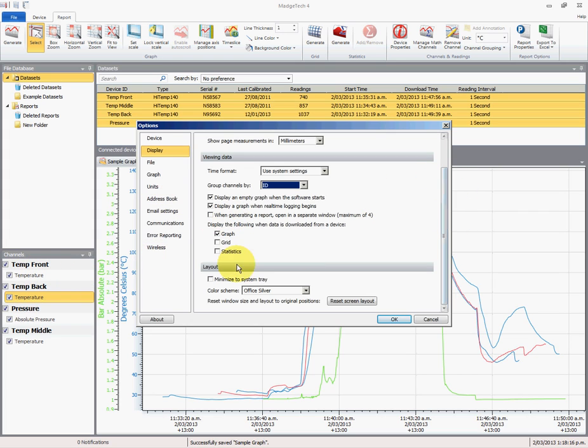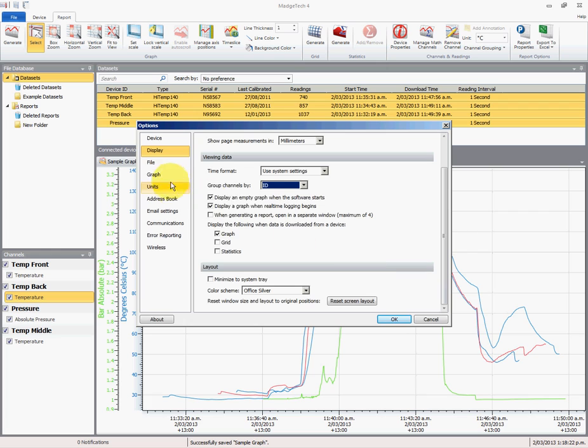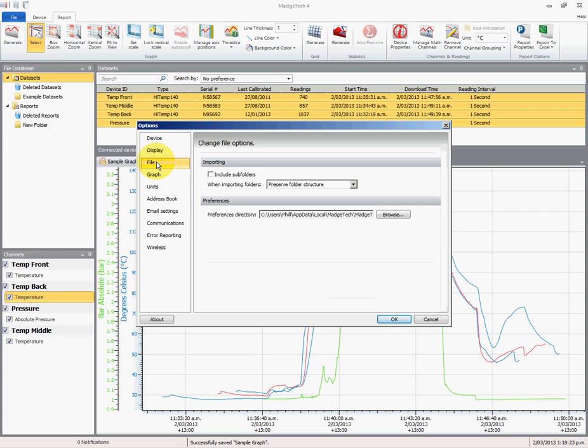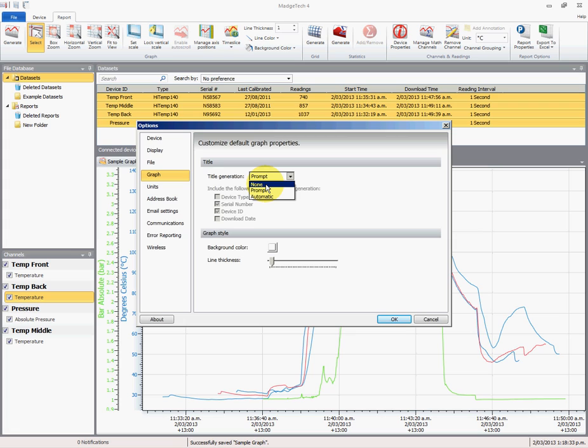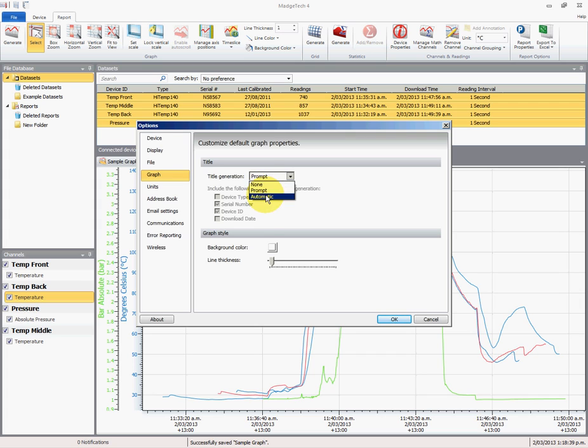When we import the data from a data logger, we're automatically going to create a graph. And the next one, we'll go to file, graph—this is where it's prompting me for the title. We can change it to have none, which would be untitled graph, or prompt, or automatic. If we select automatic, we can use the serial number and the device ID to create the title for the graph that it's going to create.